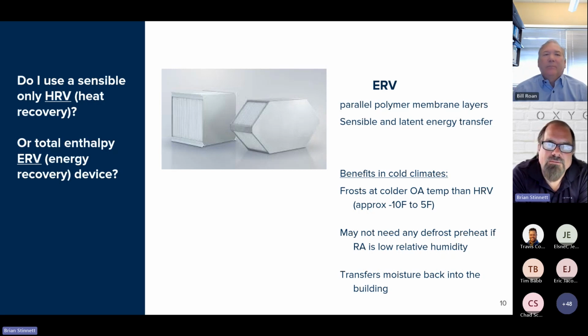Here we're talking about an enthalpy device using a polymer film. It's a thin plastic membrane. It allows moisture and temperature transfer. Still zero cross-contamination in the core. But the benefit is, rather than a frost temp somewhere between 20 and 30 degrees, now I'm talking about a frost temp somewhere between -10 to +5 degrees.